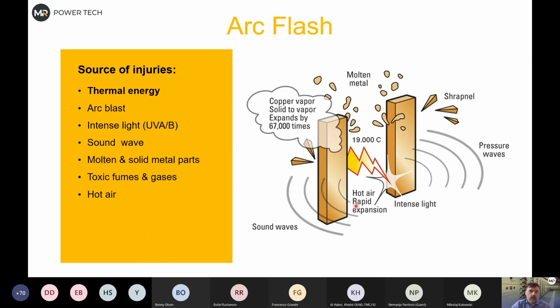Next thing is hot air rapid expansion. There are a few things related to temperature here. The temperature itself causes vaporization of aluminum or copper, depending what our bus bars are made of, which means it's expanding roughly 67,000 times. So if it goes from solid state to gas, from 1 liter of copper you might get 67,000 liters of copper gas. This is an approximation, but it gives an idea how big it will be if this expands inside the enclosure, inside the switchgear.